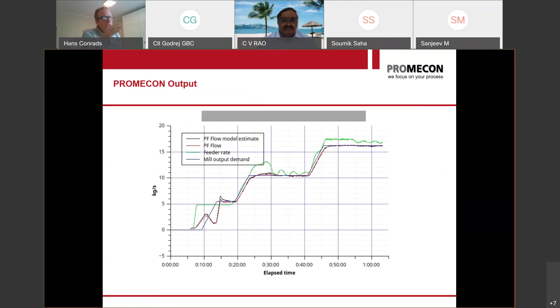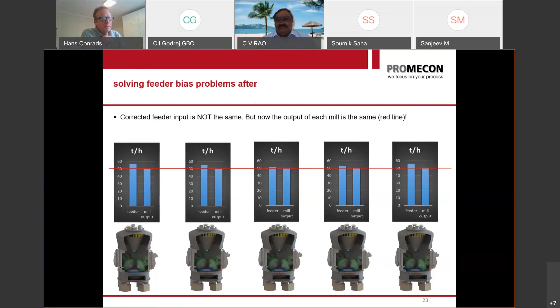Let me show you what that means mill to mill. Today, you control each mill with the same feeder setting. In the future, you'll control differently: each mill will have a different feeder setting, but you'll ensure the coal output of each mill is the same. This helps you control the coal much better in the boiler.